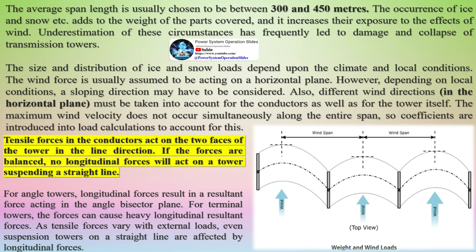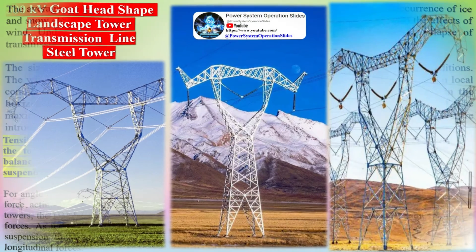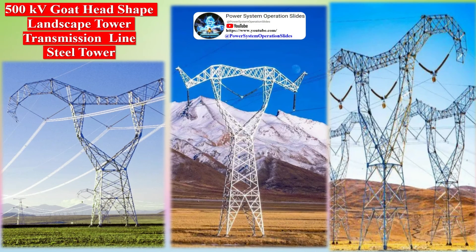The average span length is usually chosen to be between 300 and 450 meters. The occurrence of ice and snow adds to the weight of covered parts and increases their exposure to wind effects. Underestimation of these circumstances has frequently led to damage and collapse of transmission towers.